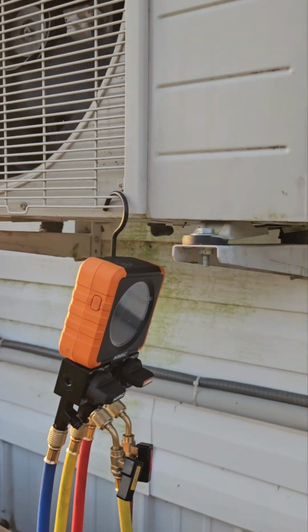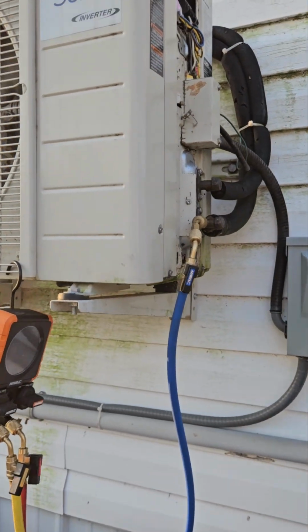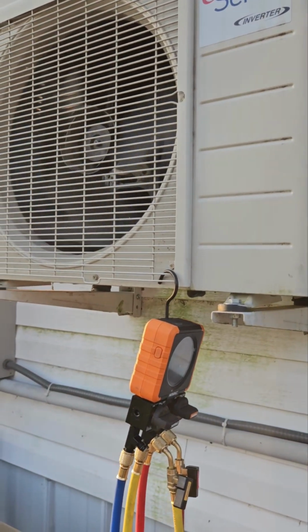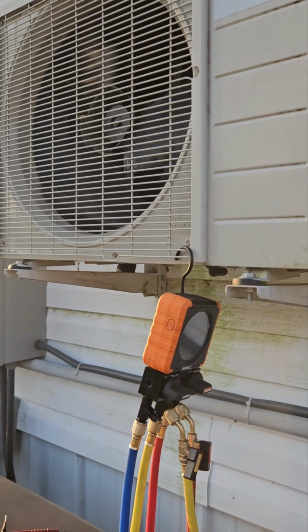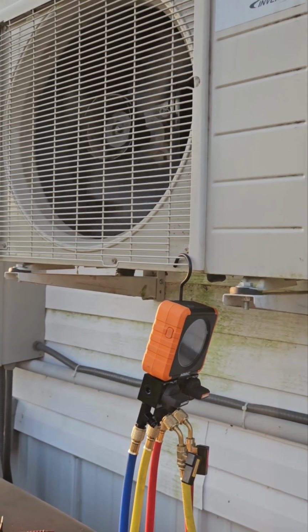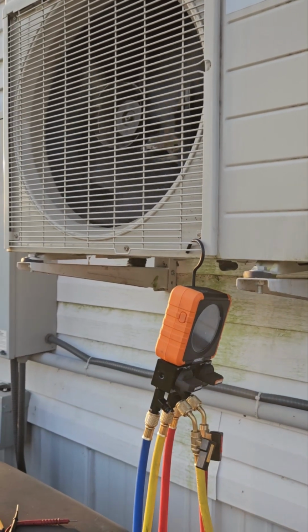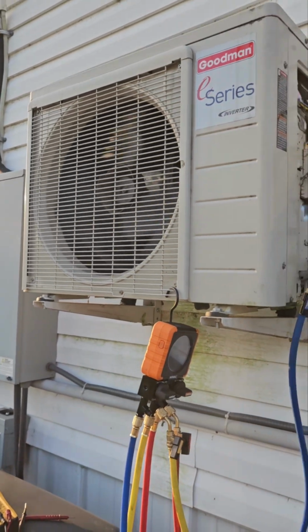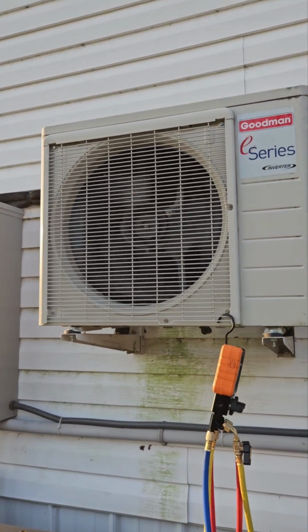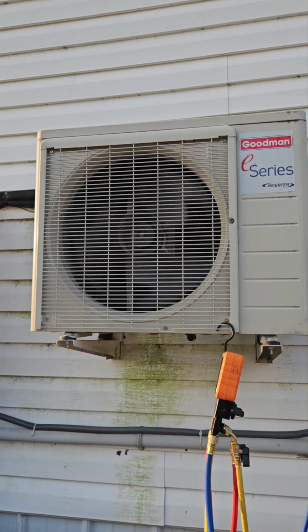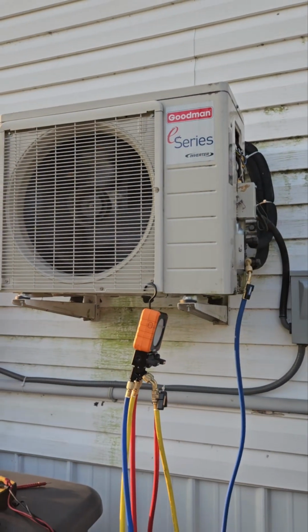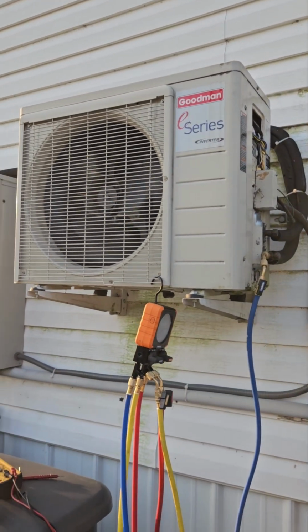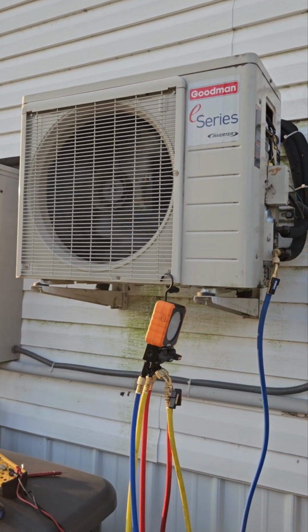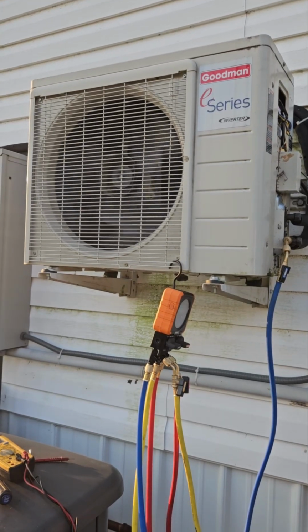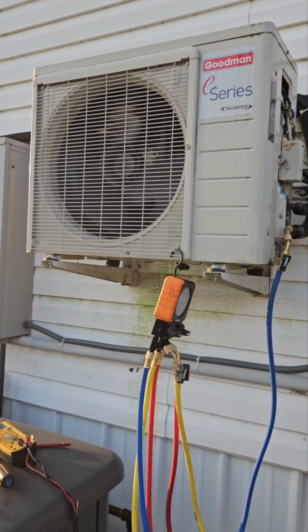So all in all, it looks good. I guess I'm just going to have to sit and babysit it for a little while and see if the fan motor stops, does the compressor stop, and then wait till it stops again to see if I can get the fault codes out of it again. So that's kind of where we're at. I'm not really seeing anything yet. I'm hoping it's just the thermistor. I'm going to let it run and come back after a bit. Hopefully it stops, but on the other hand, I hope it don't.